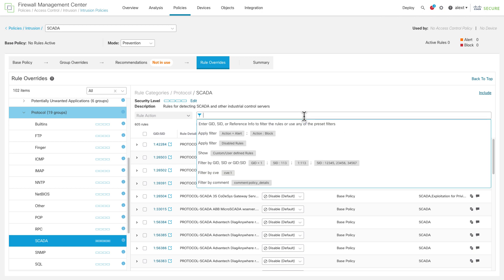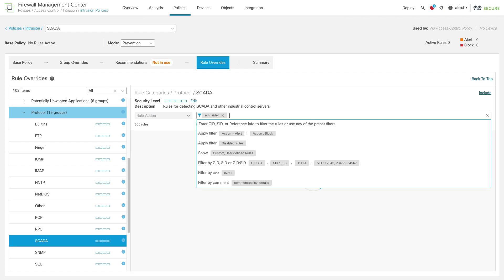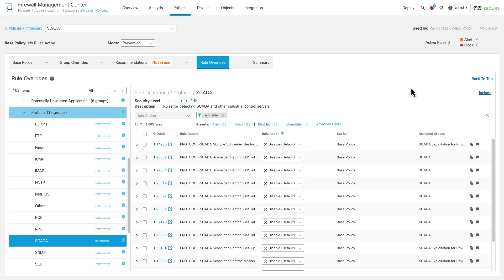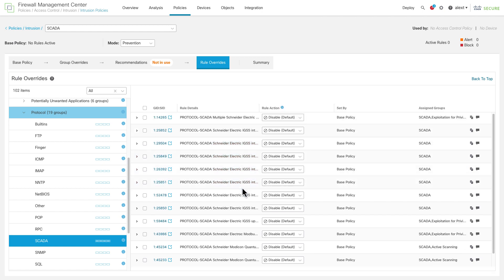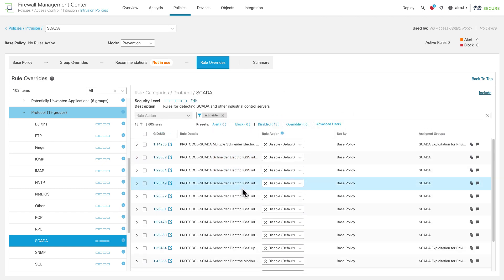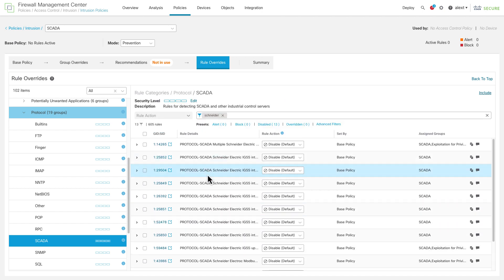You know what products you have, you know what vendors you're using on your control network. So what you can do is you can go in here and search for that. So if you know you have Schneider controls, for instance, we'll search for that. You can see there's 13 rules here for a Schneider control system, Schneider Electric. So let's say that you knew you have this particular system, then you can enable these rules.